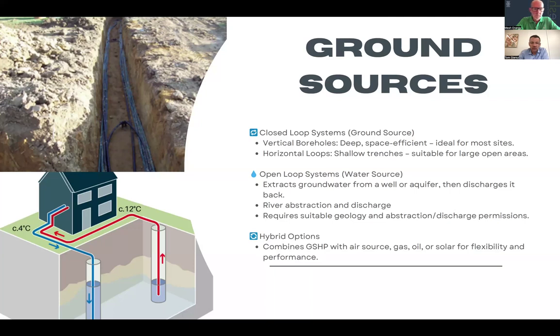And then hybrid options, which combine ground source heat pump with air source heat pump, gas, oil, or solar. Let's say you cannot upgrade the radiators, or the flow temperature required is too high for the heat pump to manage. You might say at 5 degrees outside, we are going to switch off the ground source heat pump unit and move on to oil or gas boiler. But that is still more efficient, because the majority of the time temperatures are above that, the bivalent point. So you're still improving the efficiency of the property.